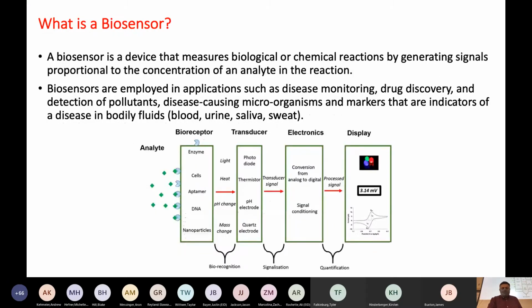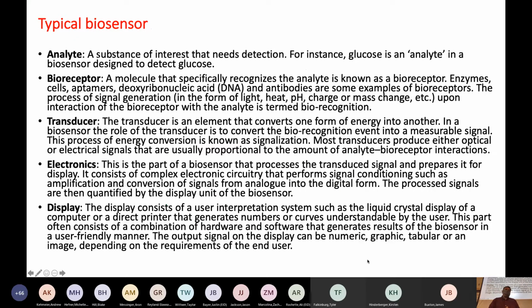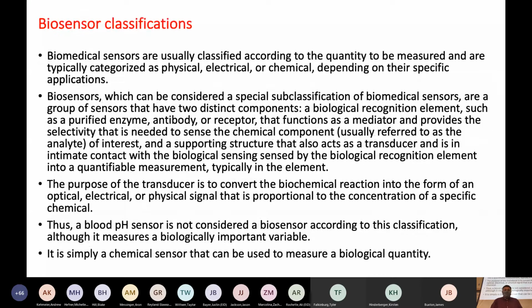So that's typically what a sensor includes: the analyte, which is important, the bioreceptor, the transducer, the electronics, and then the display. The bioreceptor is involved in the biorecognition process, the transducer in the signal transduction process, and the electronics in the quantification process. The display just shows what that is. It could be a number, a colored chart, or some sort of a graph. That's how you know that this process has happened, and you can also quantify the amount of the analyte that you're trying to get.